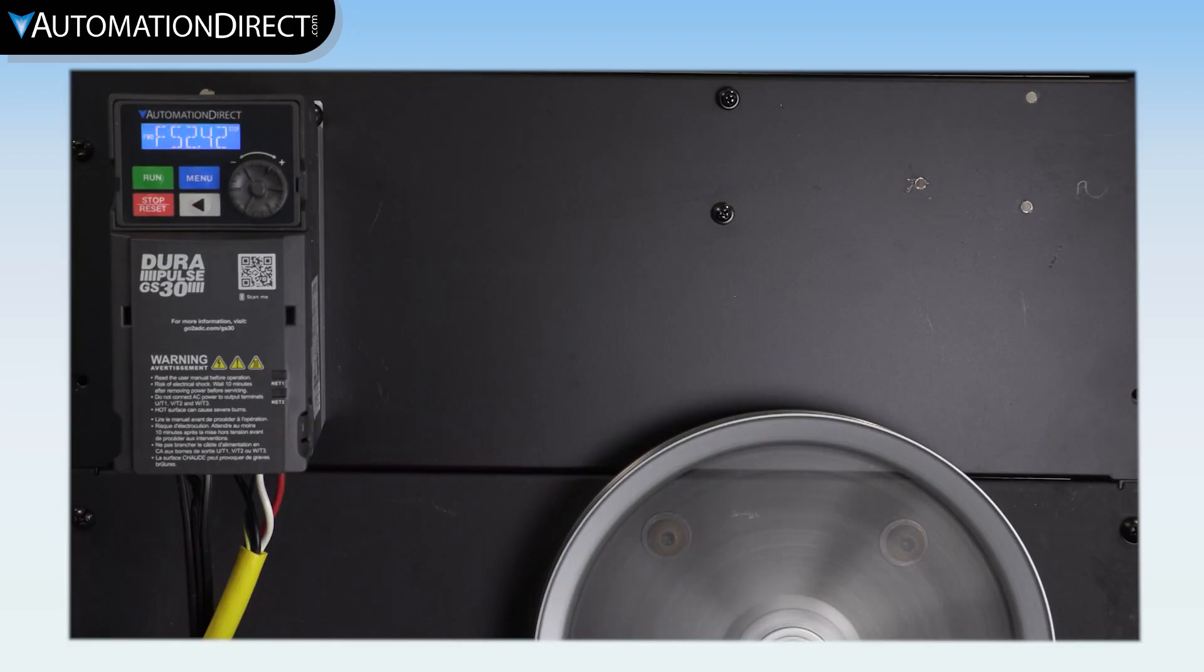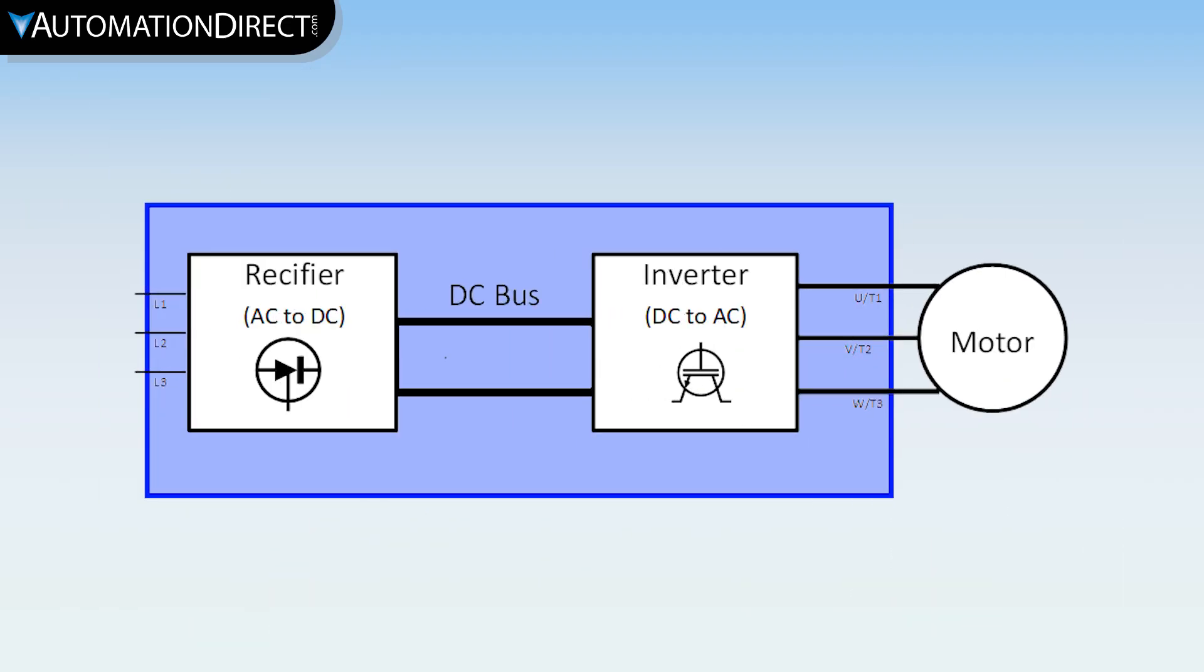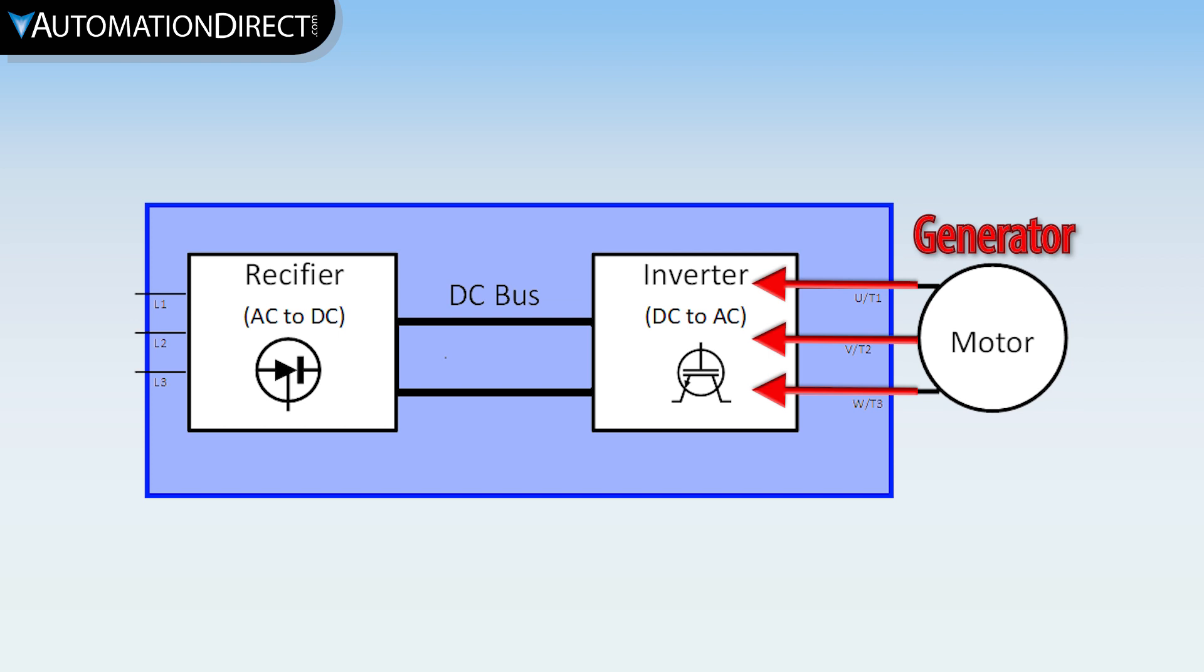When a drive slows or stops a motor, the motor can actually act as a generator and send current back into the drive. This is called regenerative voltage and is actually what is used in hybrid and electric cars to recharge the batteries.